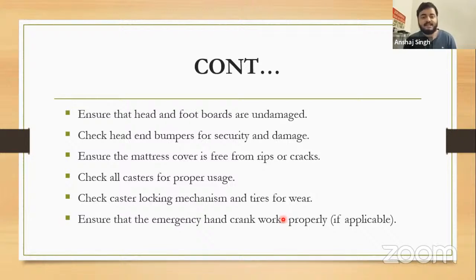Ensure that head and foot boards are undamaged. Check head end bumpers for security and damage. Ensure the mattress cover is free from rips or cracks. Check all casters for proper usage. Check caster locking mechanism and tires for wear. Ensure that the emergency hand crank works properly.